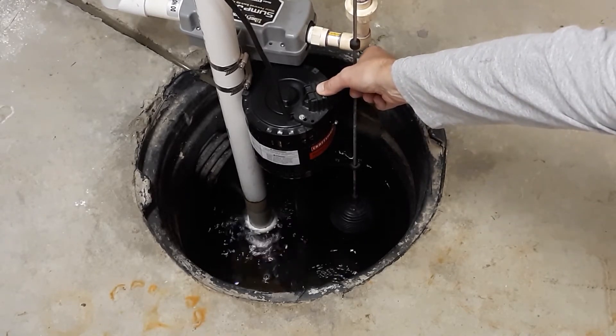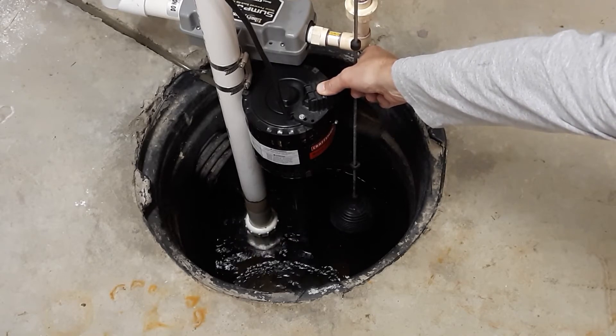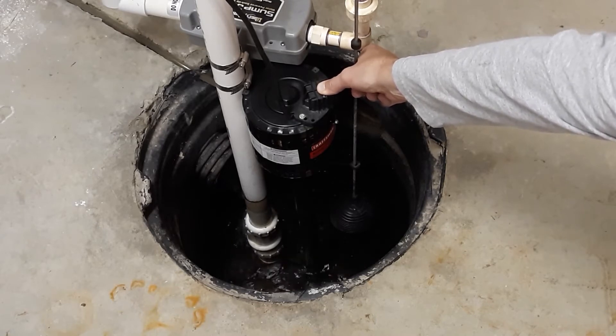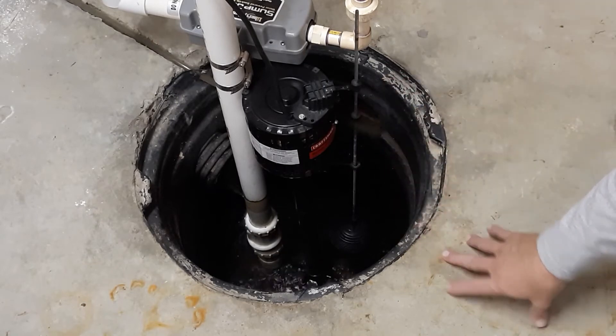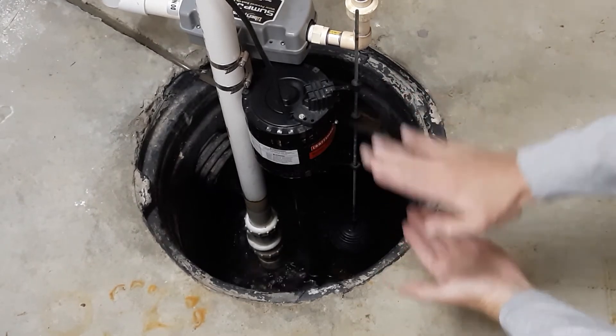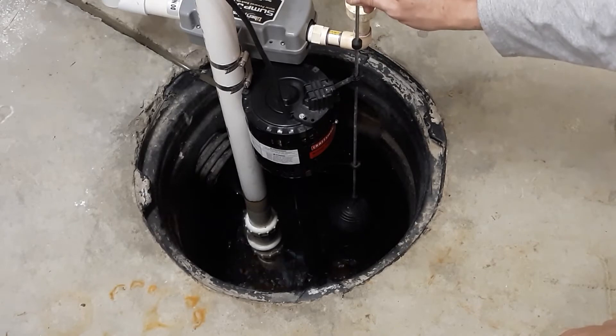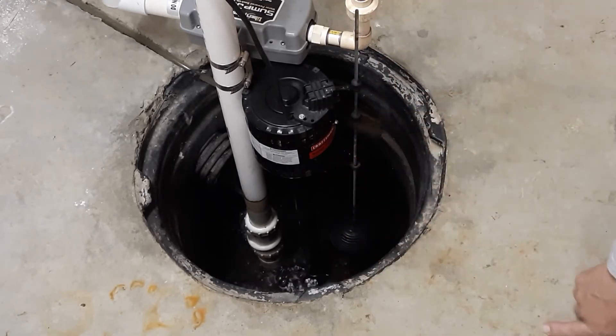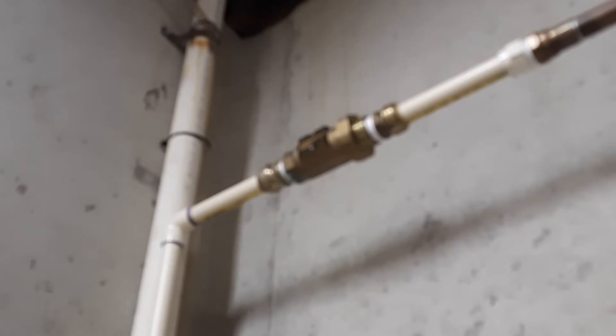Make sure you're turning your switches off and on. I'm going to drain this all the way down to the bottom — you'll hear a gurgle. The function of a pedestal pump is for quicker discharges. With a small pump it would just keep cycling on and off and burn out quickly. A pedestal pump has more travel for the float to go all the way up and trigger. I have the float set a bit higher since we have so much rain coming in — sometimes you can let it equalize, but this isn't slowing down anytime soon.